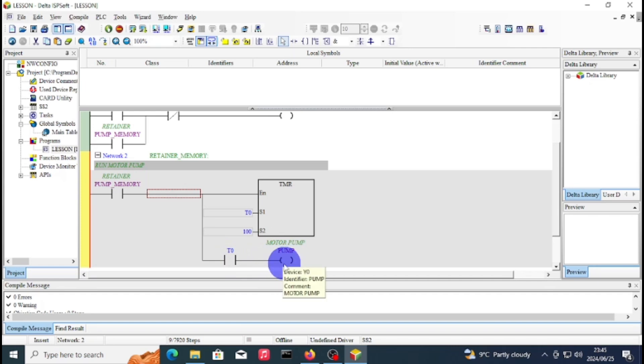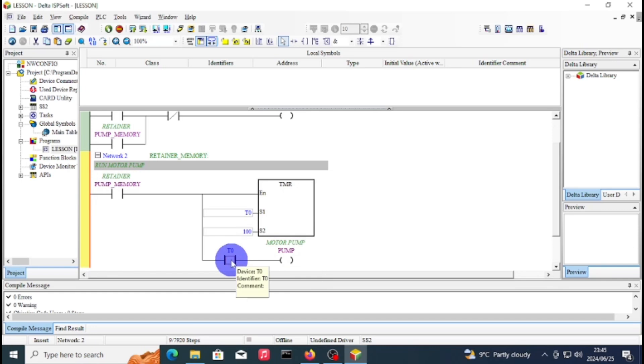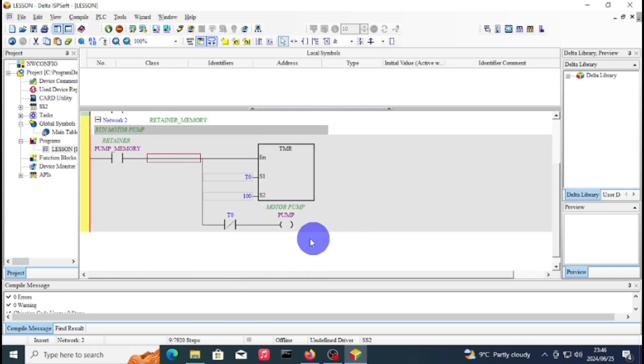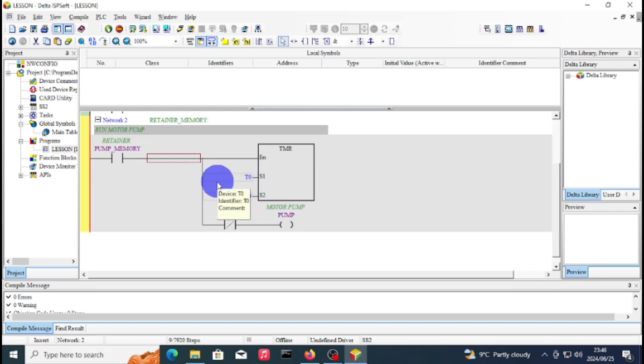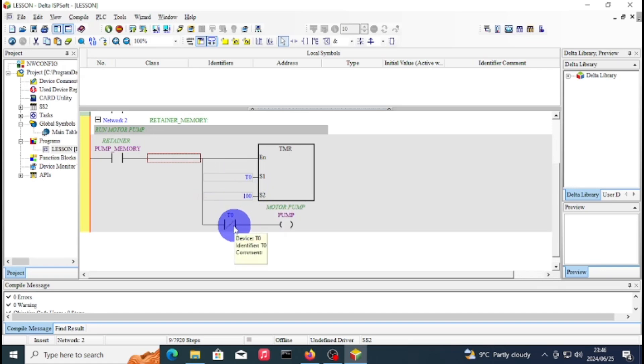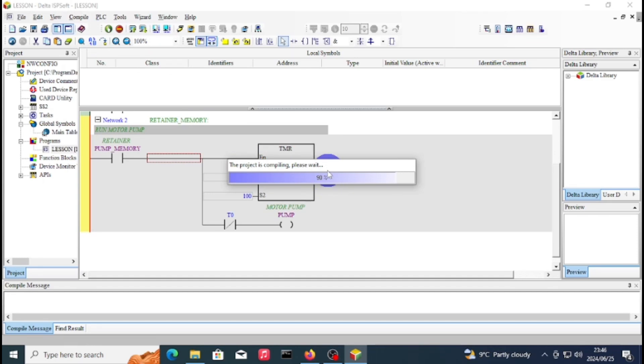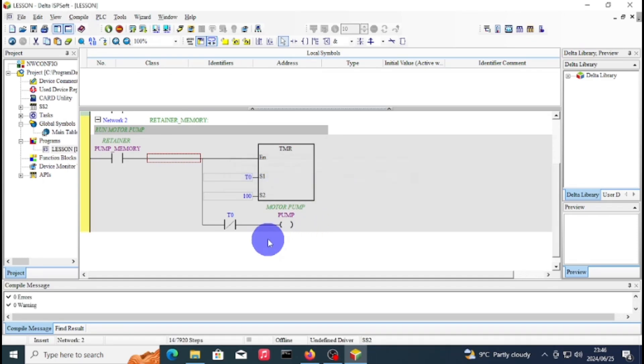If you want an off-delay, that means your timer runs first before your pump runs, then you'll put a normally closed contact. When your pump memory is enabled, the timer will count for 10 seconds and then T0 will open for those 10 seconds and your pump won't run. After 10 seconds is finished, then your pump will run.